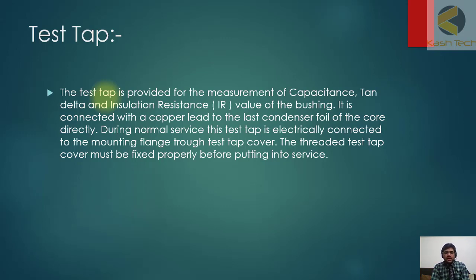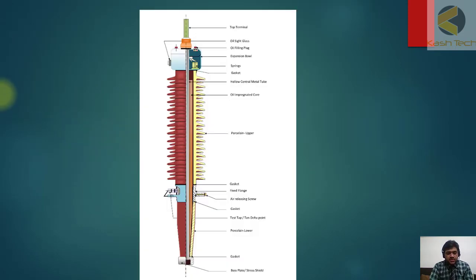It is connected with a copper lead to the last condenser foil of the core directly. During normal service, this test tap is electrically connected to the mounting flange through test tap cover. The threaded test tap cover must be fixed properly before putting into service.